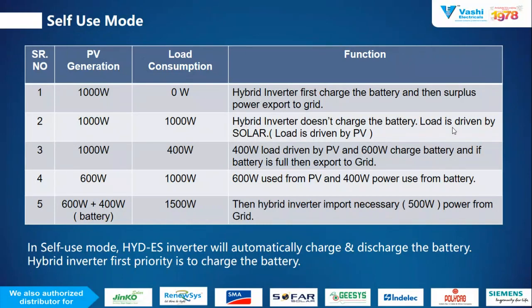Your PV generation is less, that is 600 watt, and load consumption is 1000 watt. It means your load is higher compared to your generation. In this condition, 600 watt is used from the PV and 400 watt is used from the battery. So this is the condition where load consumption is higher compared to the PV generation.